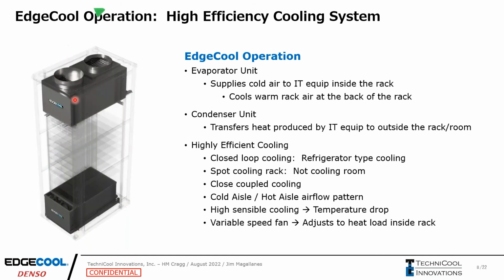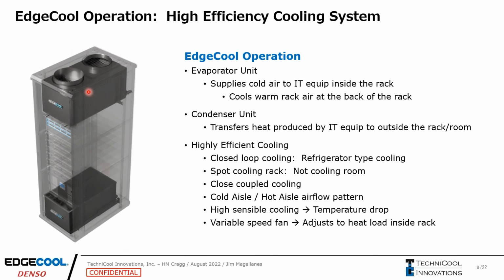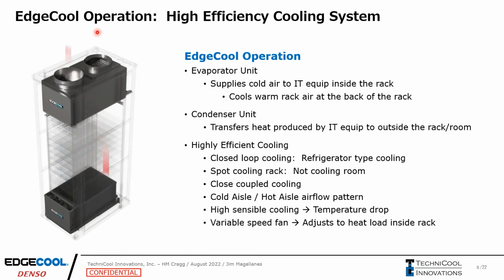And this is showing the evaporator, the condenser unit inside the rack installed. And this gets in outside air, brings that in, absorbs that heat that's being produced inside the rack, and then that red arrow shows it's exhausted outside the room or outside the rack itself.